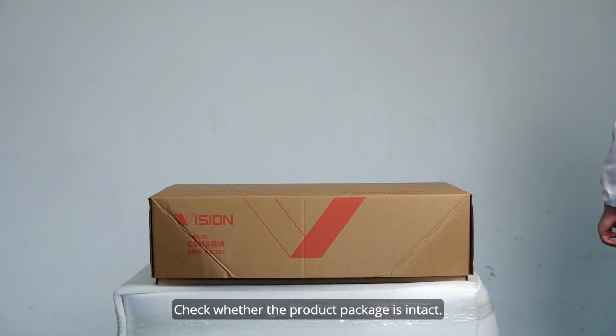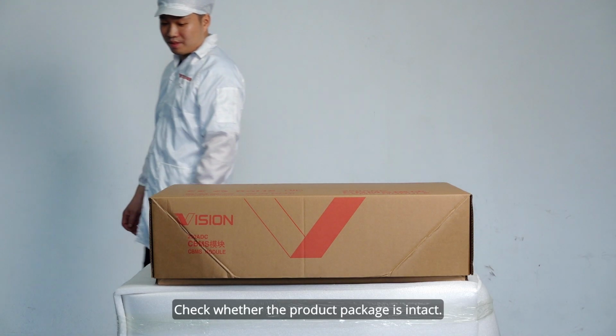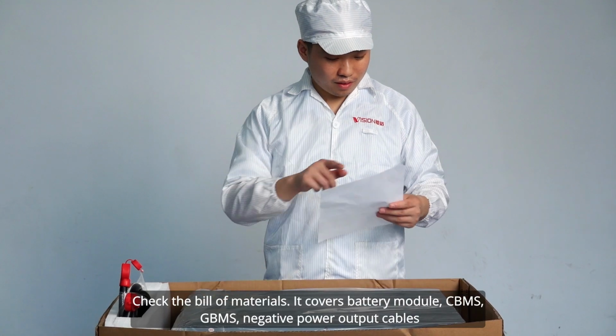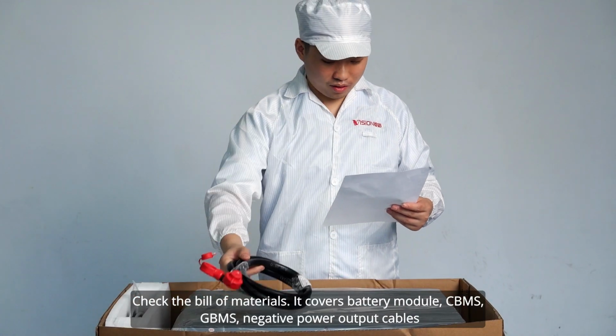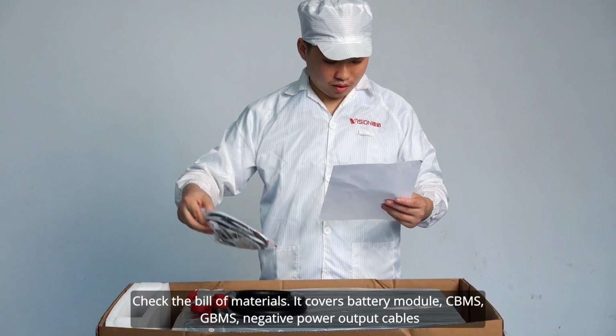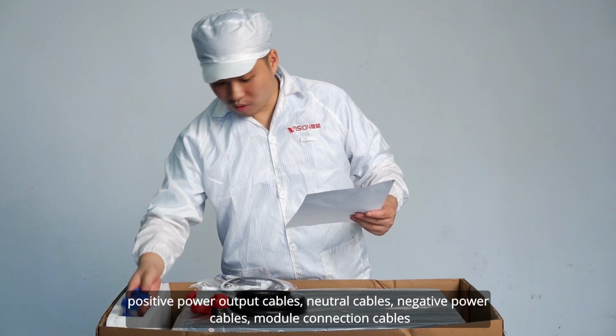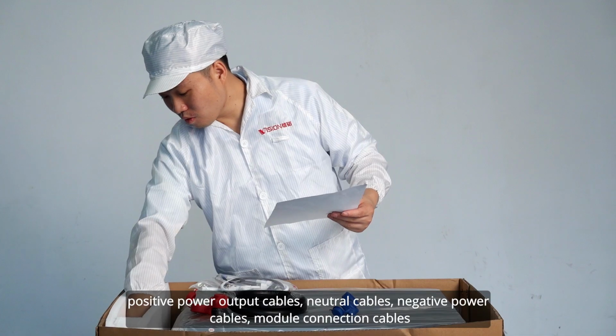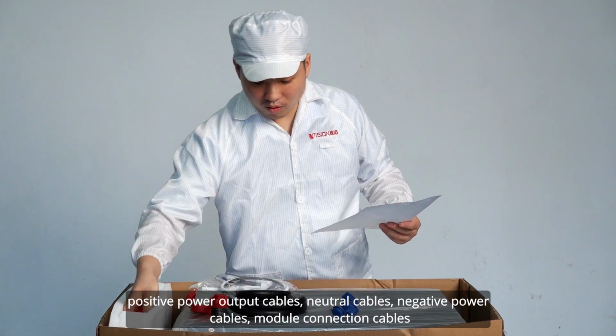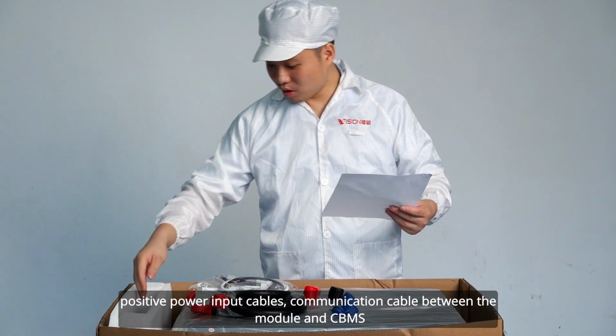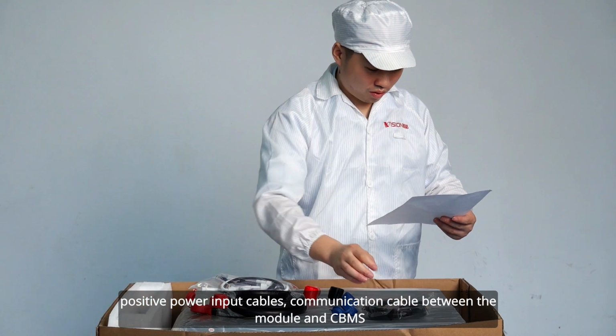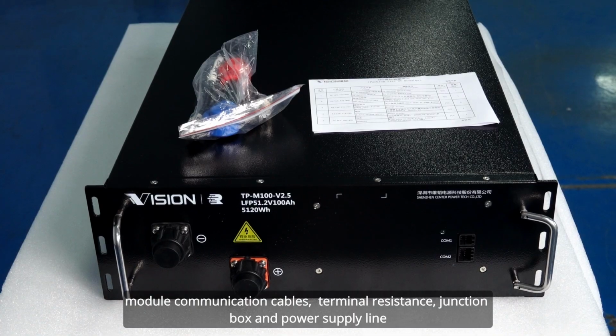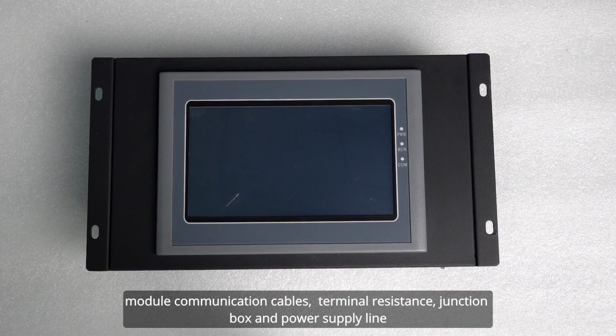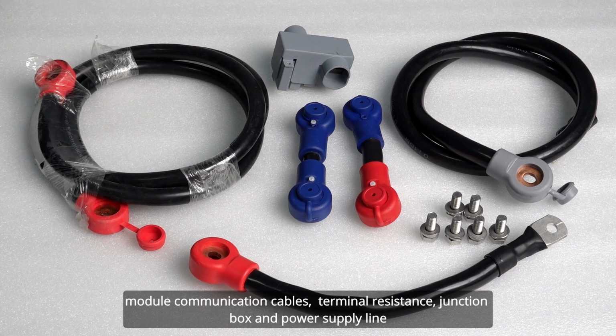3. Installation procedures. Step 1. Unpacking and checking. Check whether the product package is intact. Check the bill of materials. It covers battery module, CBMS, GBMS, negative power output cables, positive power output cables, neutral cables, negative power cables, module connection cables, positive power input cables, communication cable between the module and CBMS, module communication cables, terminal resistance, junction box, and power supply line.